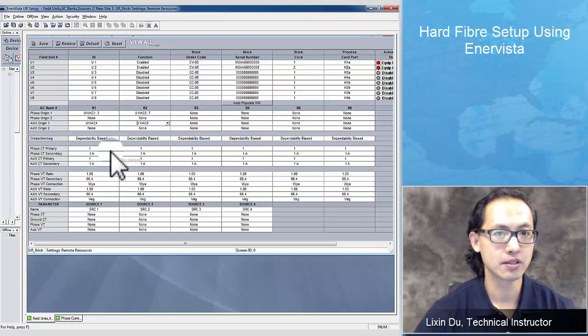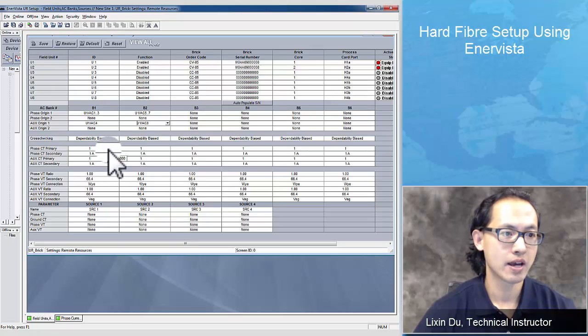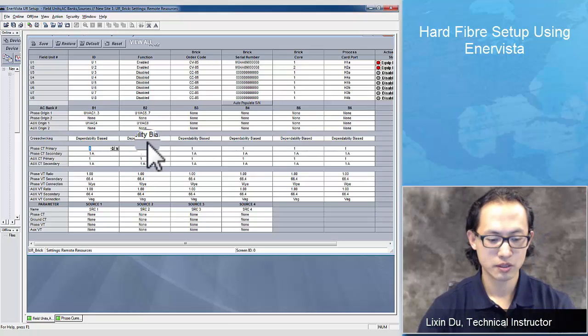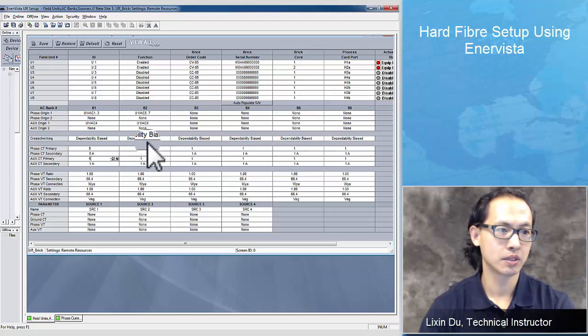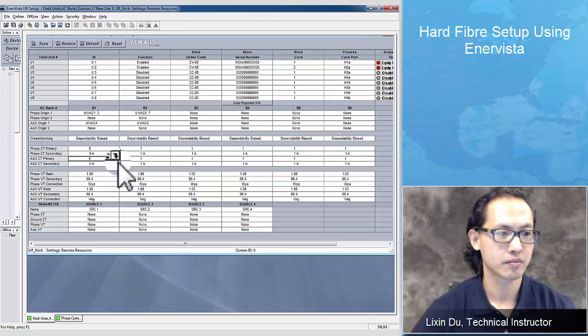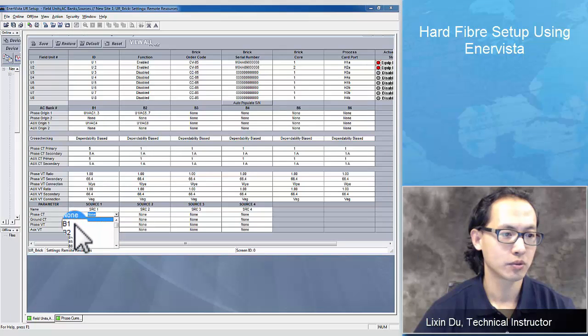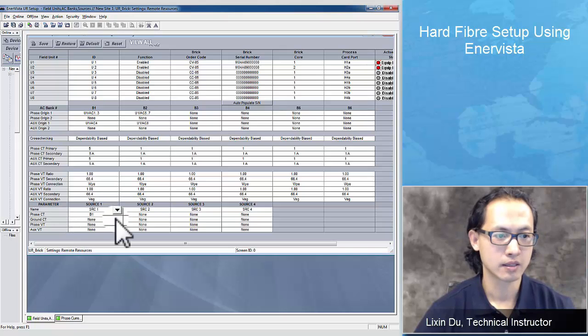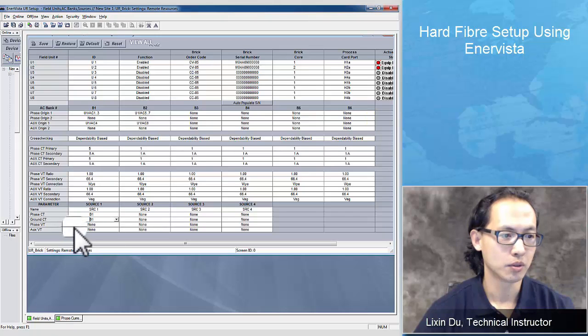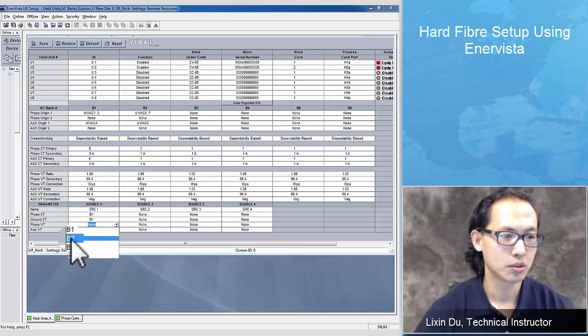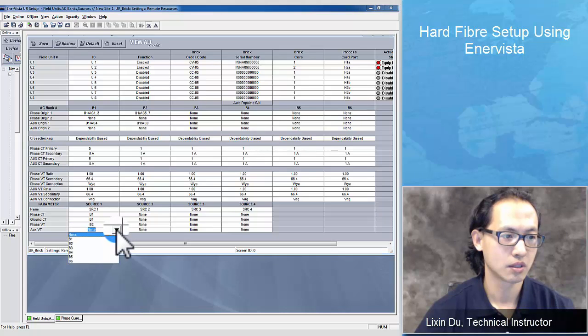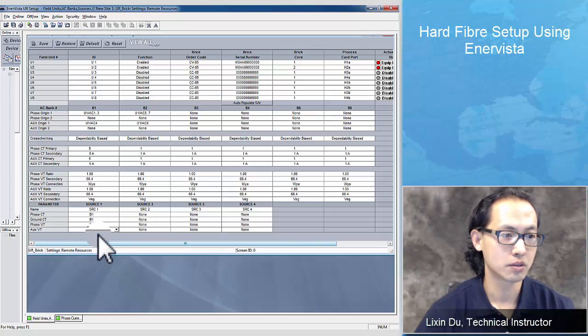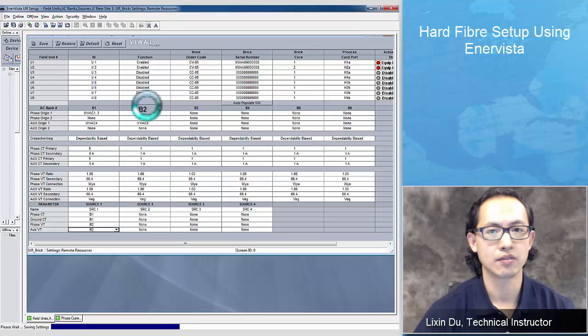For this CV05 brick, it's a 5 amp input, so I'm going to set 5 amps secondary primary for both phase and auxiliary. For the sources, I'm going to apply B1 for both phase and ground. I'm going to apply B2 for the phase VT and also B2 for the auxiliary VT and save.